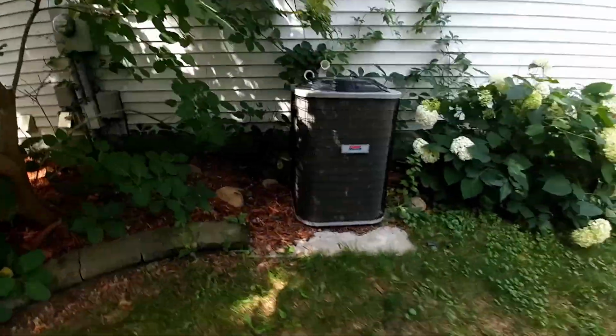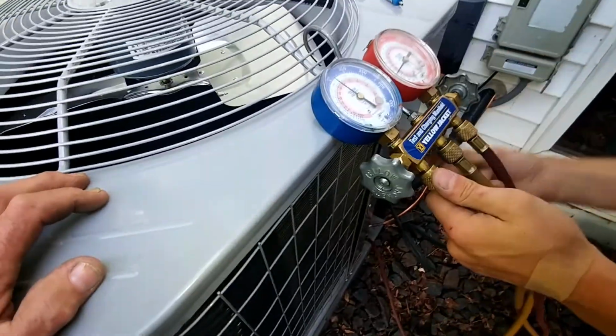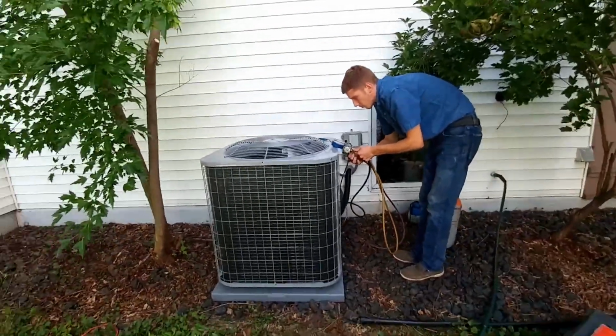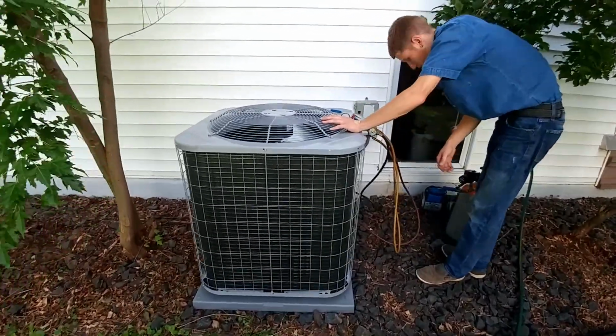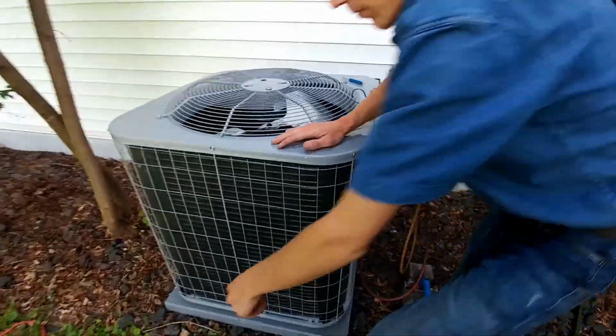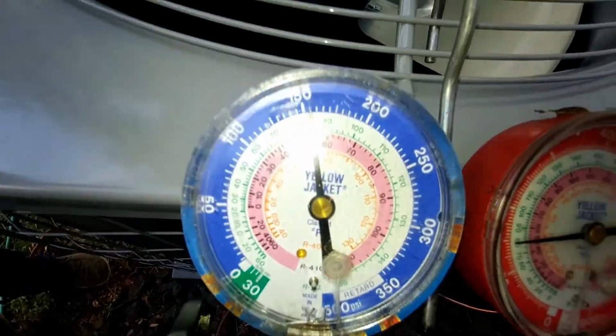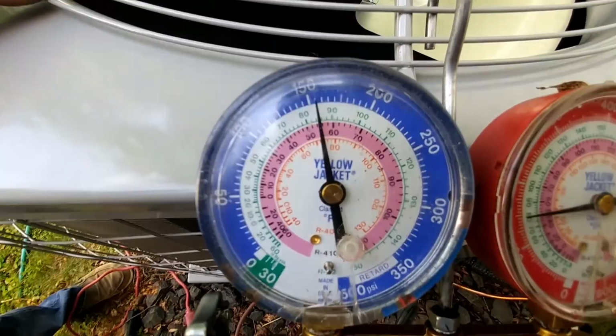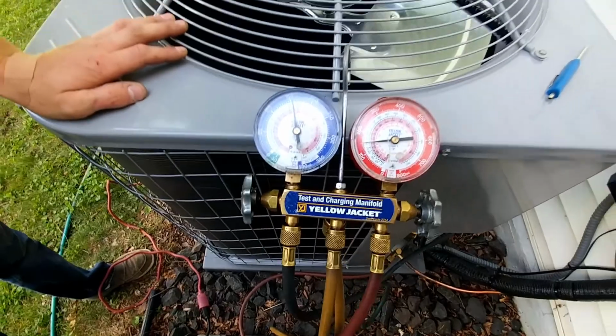So yeah, pressure testing. We got on there 155. I've been going about 200, 220. You've been doing? That's alright. Whatever. If you got a leak right now, it's pretty darn small because it ain't going anywhere. And we ain't never going to find a leak that's not going to present itself here within 5 minutes.